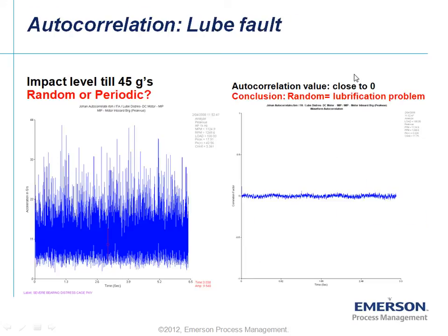Now we will take a closer look at some examples. On the left side you see a waveform — in this case a peak view waveform — with high impacting levels of roughly 45 Gs. The fundamental question is: is this data repeatable or random? If we execute the autocorrelation process on this waveform, the autocorrelation factor is close to zero, so we have a lubrication issue.